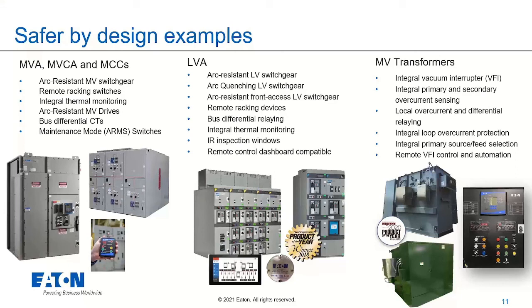On the transformer side, which is what we'll focus on for the remainder of the presentation, we're looking at integrated equipment - integrated vacuum interrupters, the VFI or vacuum fault interrupter. This integrates overcurrent sensing and relaying into the transformer, and also does similar remote racking or remote switching. What we can do with that technology, implemented in a transformer or substation lineup or whatever your MV gear is, is truly benefit you from an arc flash perspective.